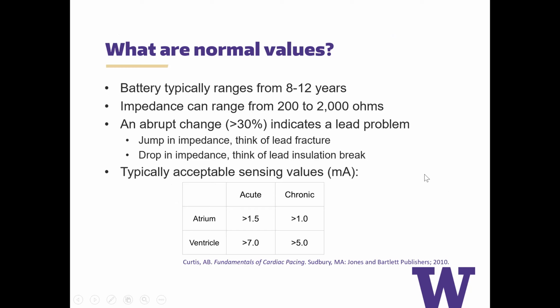So what are normal values? Battery life typically ranges anywhere from 8 to 12 years. That's really good nowadays for our pacemaker patients. Normal impedance ranges from 200 to 2000 ohms. Whenever you have an abrupt change in lead parameters, like greater than 25 or 30%, you have to think about a lead problem. A sudden jump in impedance suggests a lead fracture, and a sudden drop in impedance suggests a lead insulation break or a lead break.